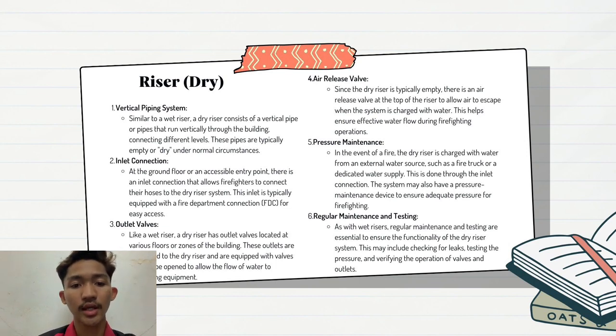Fifth, pressure maintenance. In the event of a fire, the dry riser is charged with water from an external water source, such as a fire truck or a dedicated water supply. This is done through the inlet connection. The system may also have a pressure maintenance device to ensure adequate pressure for firefighting. The last one, regular maintenance and testing. As with wet risers, regular maintenance and testing are essential to ensure the functionality of the dry riser system. This may include checking for leaks, testing the pressure, and verifying the operation of valves and outlets.